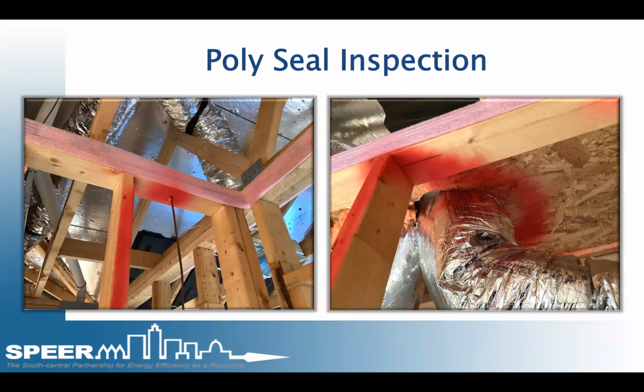Yes, they're fire rated. Yes, they stop air, but only for a snapshot of time. After the house experiences both heating and cooling, many products have expanded and contracted at different rates, and the sealing material is no longer as it was when it was constructed. We all know that wood shrinks over time. The spaces in between get further apart. Add that to the expansion and contraction of different materials, and there's no wonder a house has a higher blower door score if tested again a year after being completed.